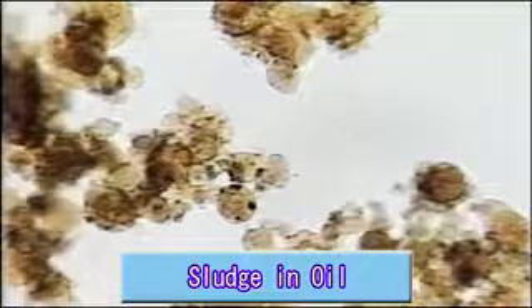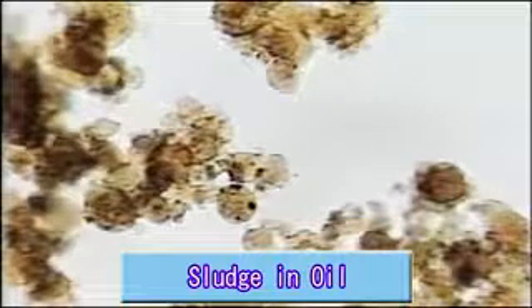Did you know that the microcontaminants called sludge in oil are the cause of machine failures and oil leaks? Let's take a closer look at the microcontaminants found in hydraulic fluid under a microscope. This is hydraulic fluid from a flow-forming machine. Here we can see jelly-like sludge.